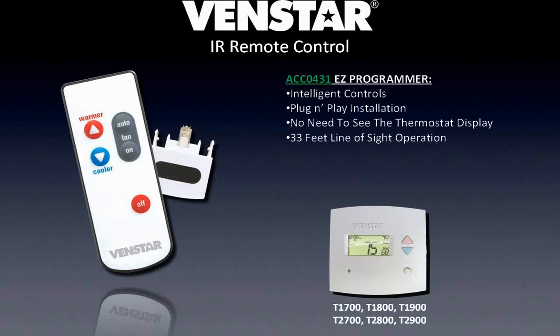There are lots of cool accessories for this stat. On the bottom there's a little phone jack-style RJ11 slot, and many accessories can plug into it. One is an infrared handheld remote — a small module plugs into the bottom of the stat, and then you have a handheld remote smaller than your cell phone. It must be in the same room as the stat, line of sight, up to about 35 feet. It can turn the temperature up or down, turn the fan on and off — just basic control. Great for a conference room, or you can train your home theater remote to control the HVAC.